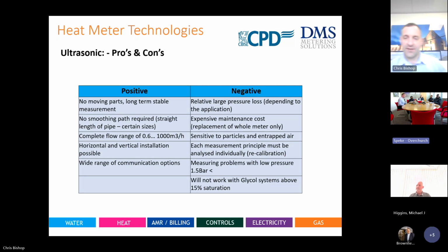And a big conversation in the industry now is glycol. So glycol is becoming more relevant. Chilled applications are becoming more relevant. So actually glycol is being added into the system. You can buy glycol solutions now that also have inhibitor mixtures, so it protects the system as well as providing frost protection at the same time. Ultrasonics have only really recently started to accept glycol programming, but you generally have to order it at point of manufacture. And if the percentage is wrong, then yet again it's a conversation with the energy provider or the energy consultant or you guys, that the meter would have to be changed because the percentage is incorrect. So yet again, it's trying to save on cost.